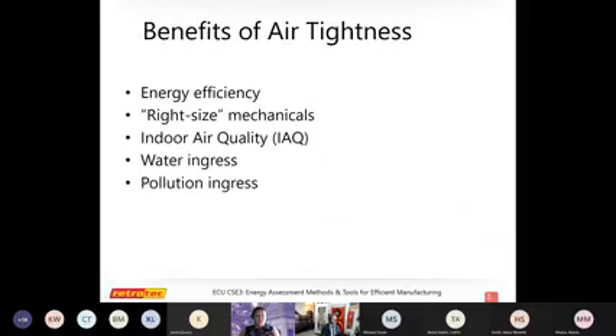So going into that, some benefits of having an airtight building enclosure: energy efficiency, of course. We're not trying to heat and cool the outdoors. Kevin talked about this load calculation that you have to do. And this is what a mechanical engineer or mechanical contractor would do to determine how much HVAC that you need for your building. And part of that load calculation is infiltration through the building envelope. And about 9 times out of 10, this is a guess.